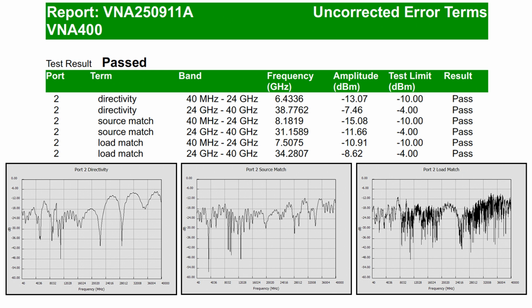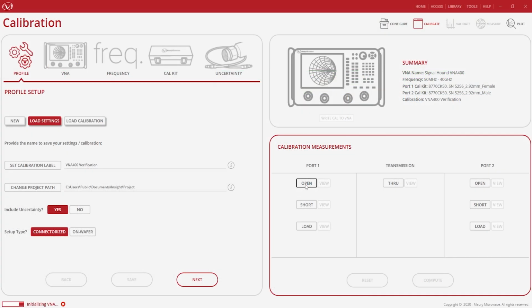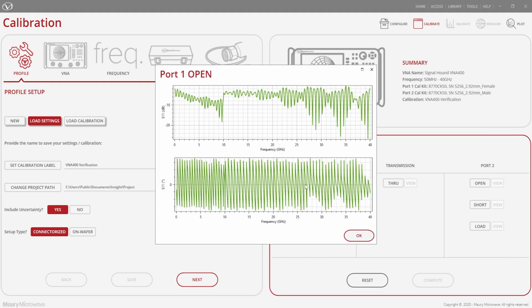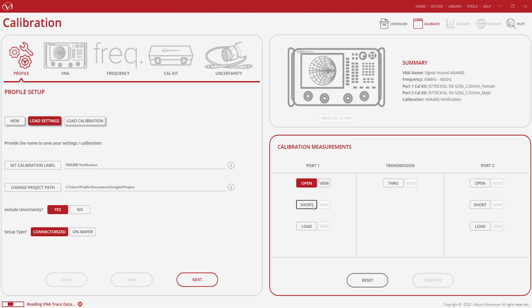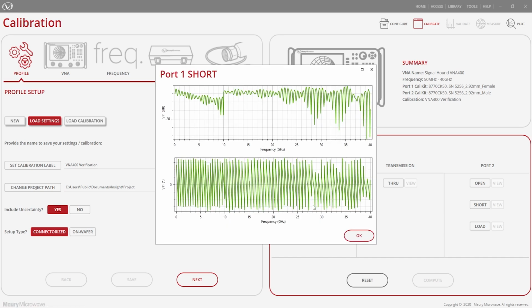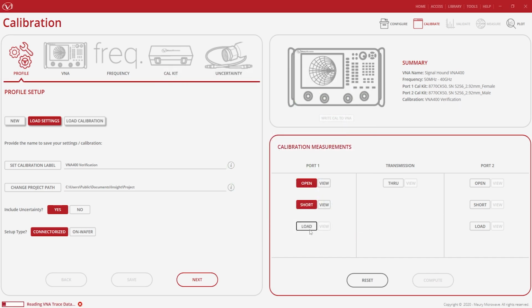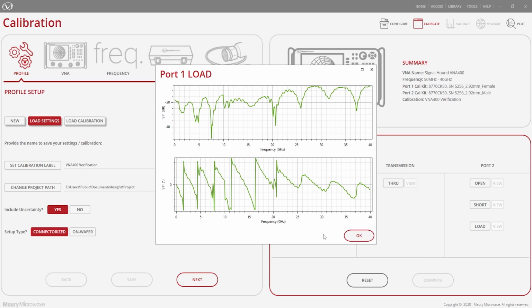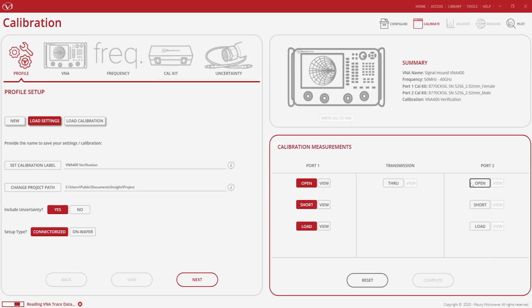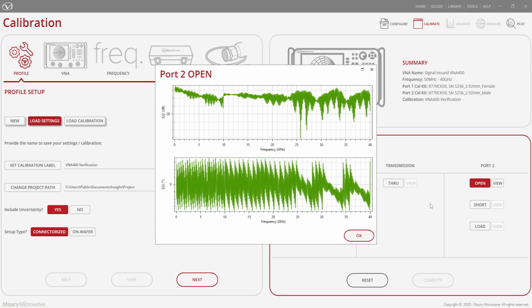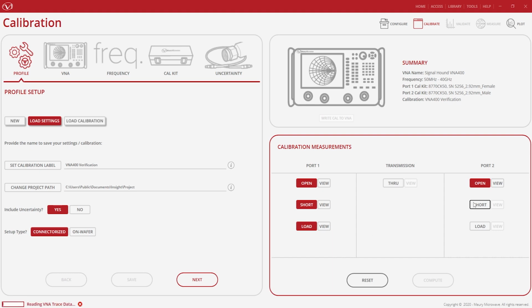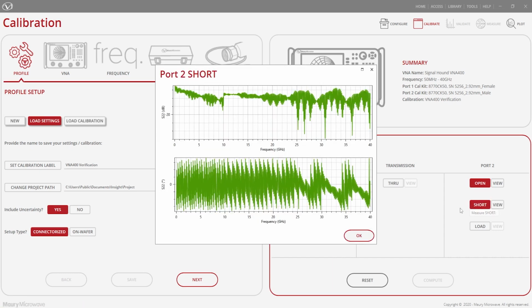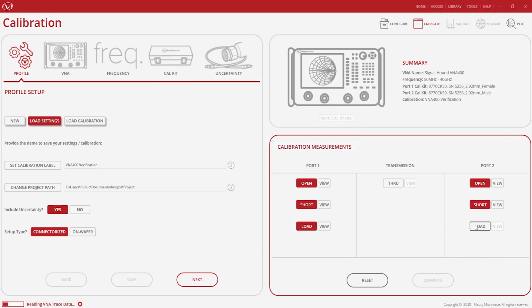unit we ship. For the final step in the verification process, we leverage Maury Insight software and a verification kit with uncertainty data. Verification standards transmit and reflect at different phases and amplitudes than the calibration standards, catching even subtle errors in your calibration. This step verifies that SignalHound's VNA400 can make accurate 1- and 2-port measurements for any device.